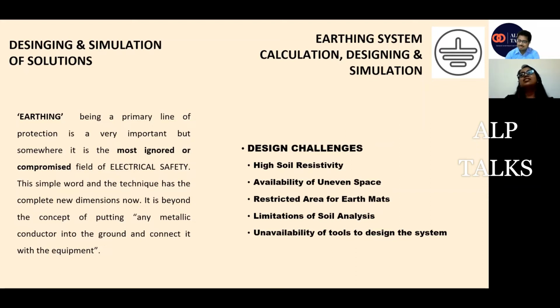The second thing is the availability of space. Traditionally, there was not so much development, so we had the area at that time, and we could do the installations. But nowadays development is so much that we do not get the space for higher resistivities to install that much of earthing. So we have space constraints, where we have only 10 by 10 meter of area, and we have to achieve the value in this only, and the resistivity is 4500 ohm meters or 2000 ohm meters. That was another challenge which we generally face. Restricted area and unavailability of even space are other issues.